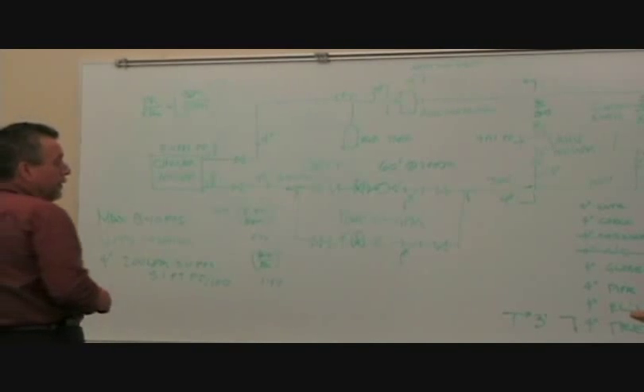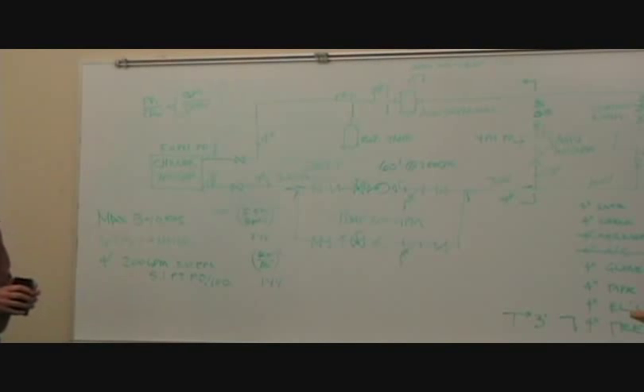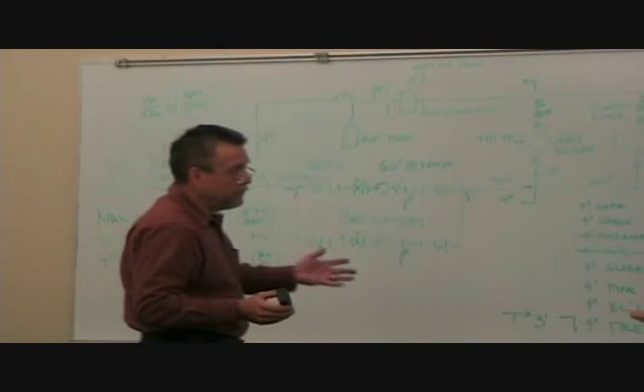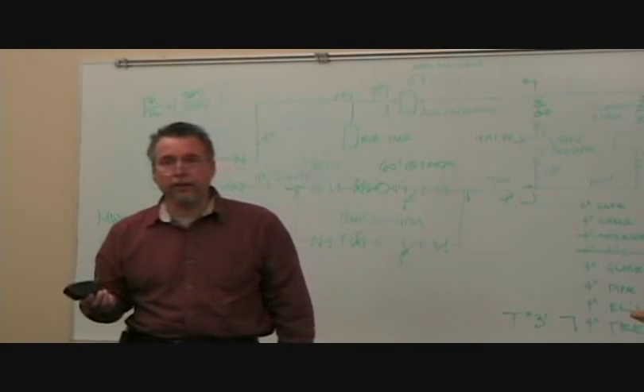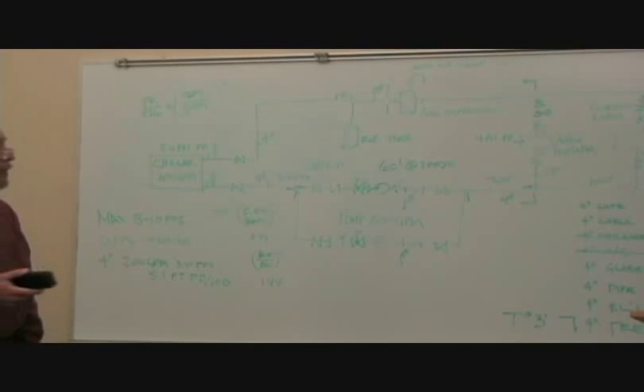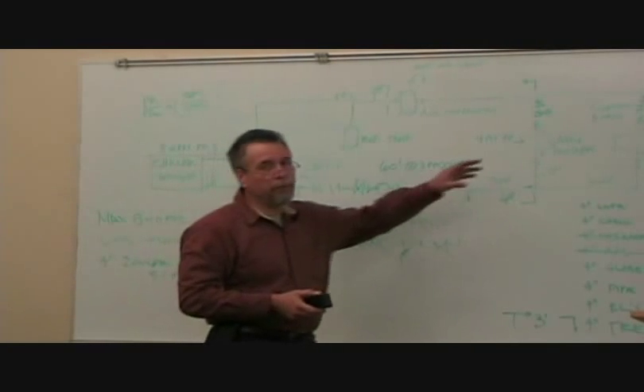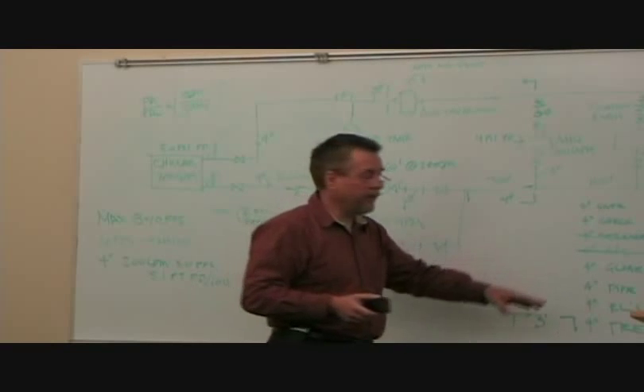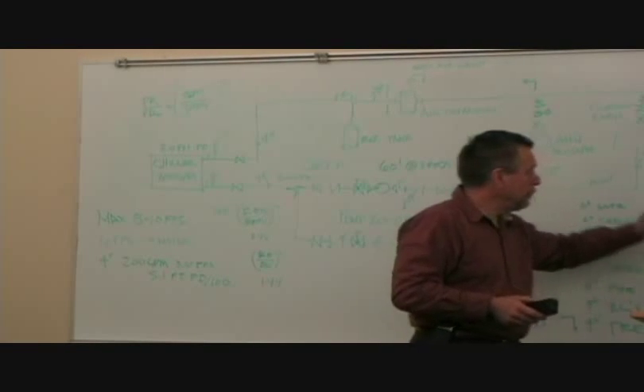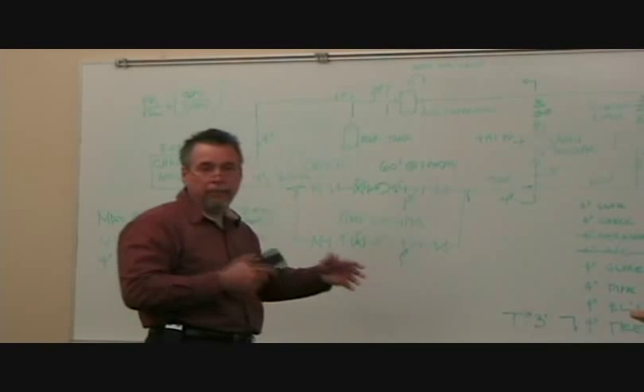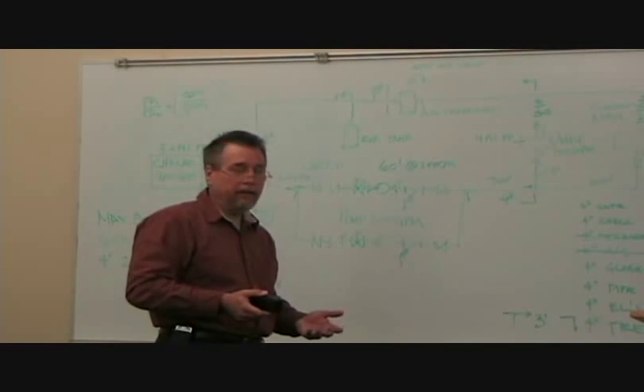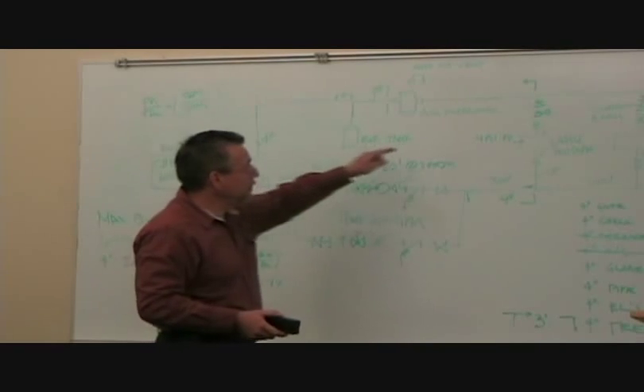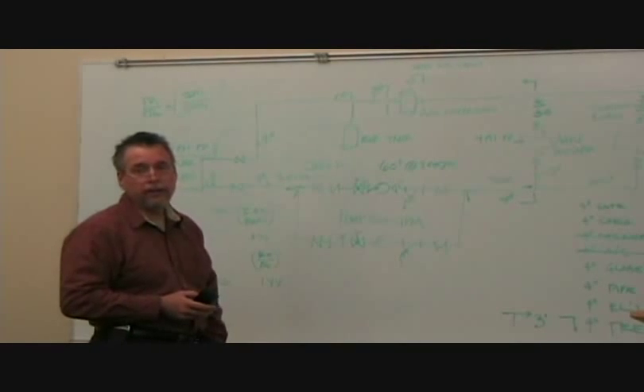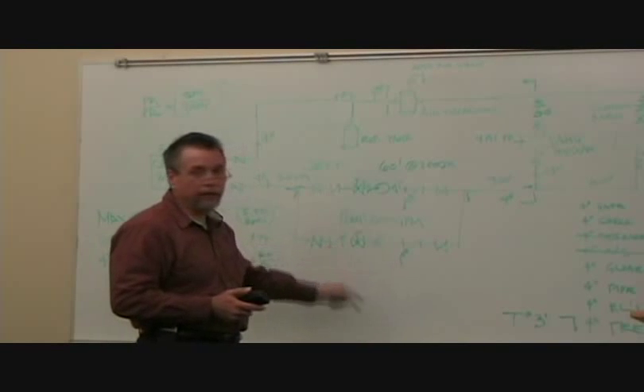Okay. Are those values pretty representative regardless of pipe size? The ratio is going to be about the same if we're going with a 2-inch system or a 12-inch system. Most HVAC systems operate in the 60 to 100 feet of head range. But comparison to fittings versus pipe, yeah. And that's the point I was trying to make, is my pipe and elbows and T's. A lot of people get real concerned about adding an elbow. It's insignificant, but these big devices are here, these coils, pressure drop, strainers, and check valves.